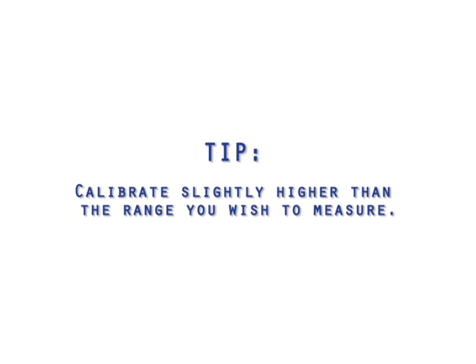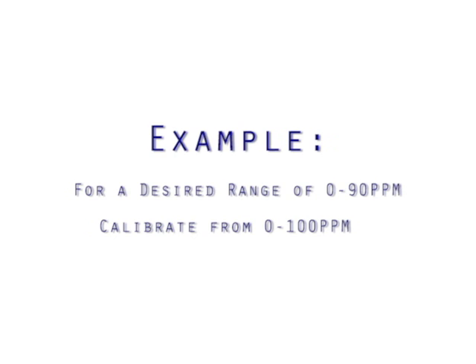As a tip, I suggest using a full-scale sample that is higher than the actual measurement range. This will allow you to read slightly above your range. For example, if your actual measurement range is 0 to 90 ppm, I would calibrate for 0 to 100 ppm.